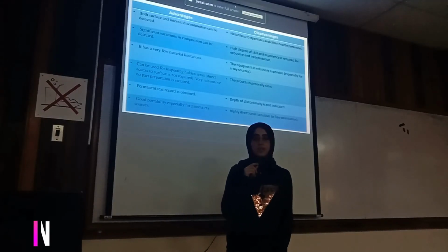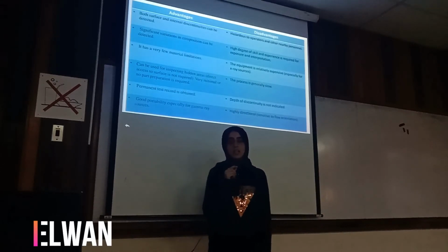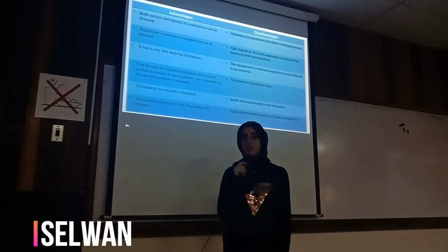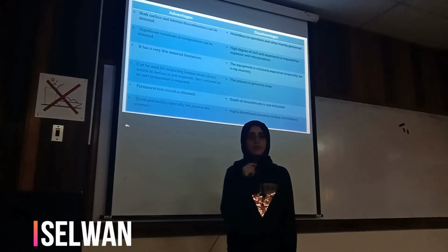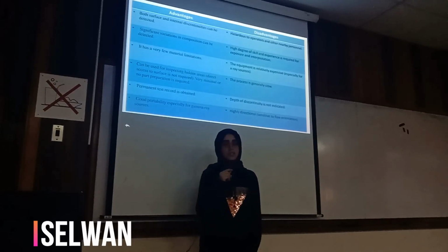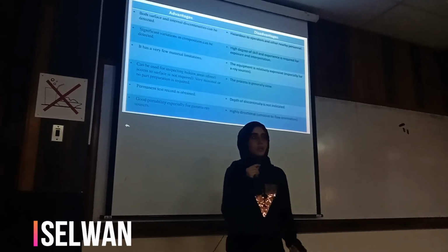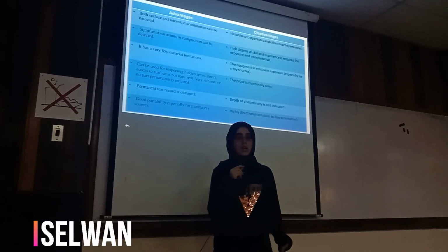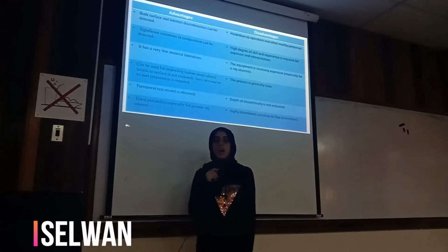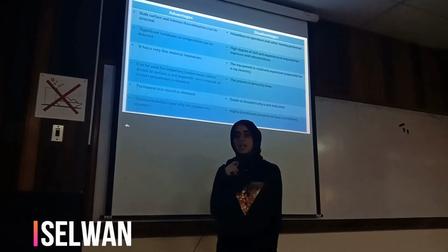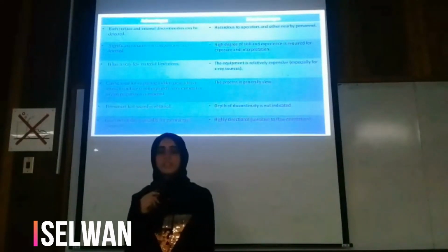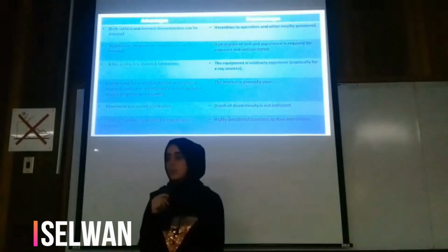So the first advantage of radiographic testing is that it can detect both internal and surface cracks, and it can also detect variation in composition, and it has very few material limitations, and it doesn't require any direct access to the surface or preparation of the surface. It can be used for hidden areas. And also a permanent testing record is obtained. The final point of this advantage is that radiographic testing can be carried from place to place, especially with a gamma ray source.